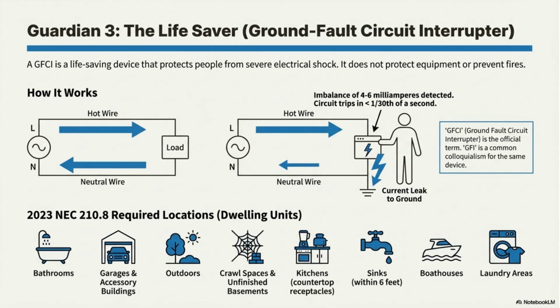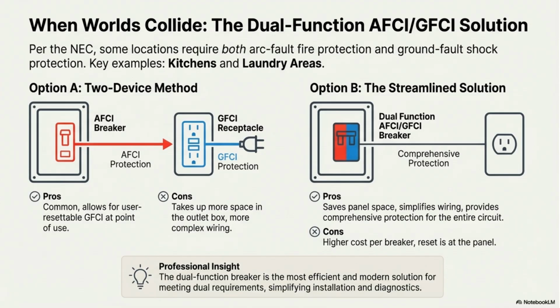Guardian 3, the lifesaver, is the GFCI. It protects people from severe electrical shock by detecting an imbalance of 4 to 6 milliamperes between the hot and neutral wires. It trips the circuit in less than 1/30th of a second. GFCI protection is required in areas exposed to water or moisture. In locations like kitchens and laundry areas, both arc fault fire protection and ground fault shock protection are required. The dual-function AFCI-GFCI breaker offers a streamlined solution, saving panel space and simplifying wiring, making it the most modern choice.